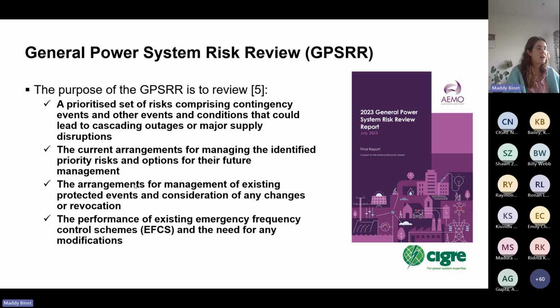Something we also want to consider is what future management arrangements we could put in place. We also look five years into the future, because if a risk is going to be alleviated by an augmentation in the next year or two, there wouldn't be much point recommending a protection scheme to mitigate it if that risk won't be in the system, or if the risk profile changes significantly within a couple of years. So generally we do current system studies, but also studies looking five years into the future.